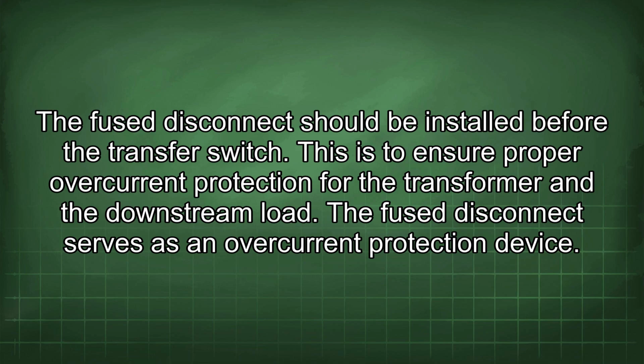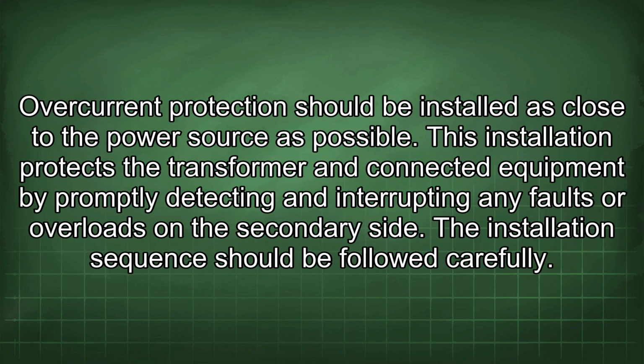The fuse disconnect serves as an overcurrent protection device. Overcurrent protection should be installed as close to the power source as possible. This installation protects the transformer and connected equipment by promptly detecting and interrupting any faults or overloads on the secondary side. The installation sequence should be followed carefully.